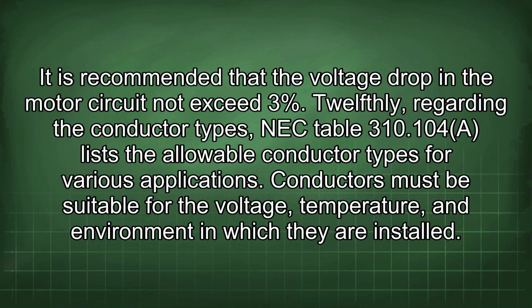12thly, regarding the conductor types, NEC Table 310.104 lists the allowable conductor types for various applications. Conductors must be suitable for the voltage, temperature, and environment in which they are installed.